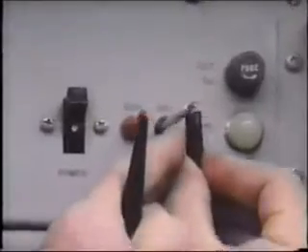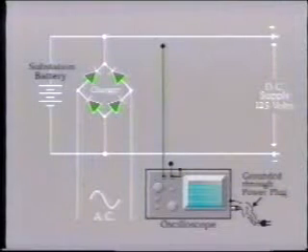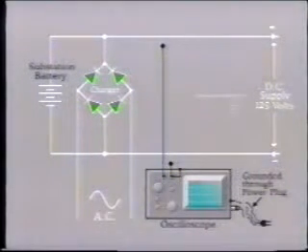Assume that a substation's solid-state equipment has been acting strangely and you are called to investigate. One possibility is that the equipment's power supply filter circuit has degraded and excessive AC ripple is interfering with the solid-state equipment's operation. You set up the scope and make the connections to look at the waveform of the DC supply. Beware! Plugging the scope's three-prong power supply plug directly into a normal AC receptacle connects its chassis to ground, effectively grounding one side of the incoming signal. Well, substation batteries and telephone circuits are deliberately isolated from ground.